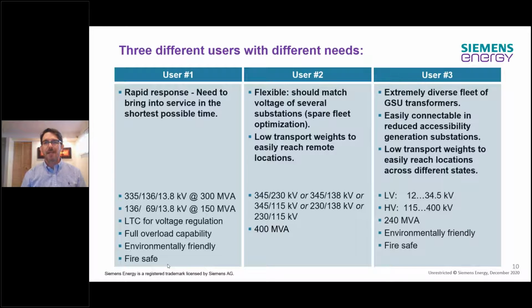And in case number 3, the challenge was, as I said, to develop a solution that would cover a very broad spectrum of low voltages from 12 kilovolt all the way to 34.5, and high voltages from 115 kilovolt to 400 kV, 240 MVA, ideally environmentally friendly and fire safe as well.